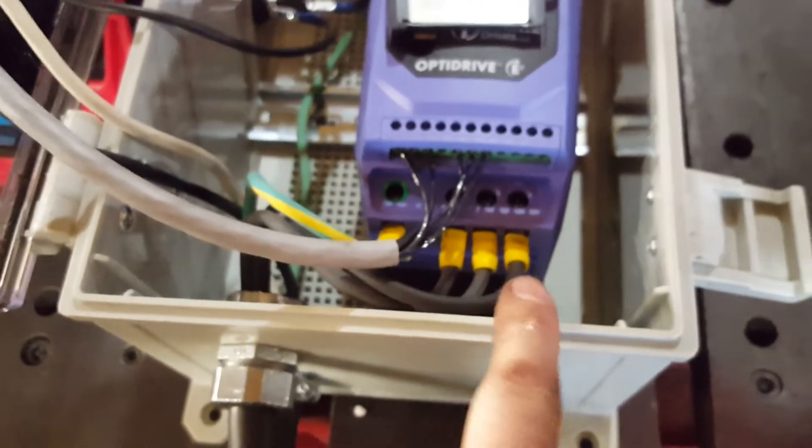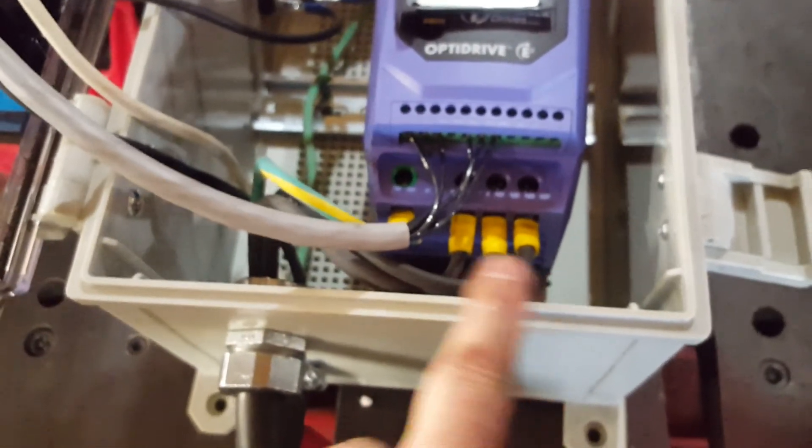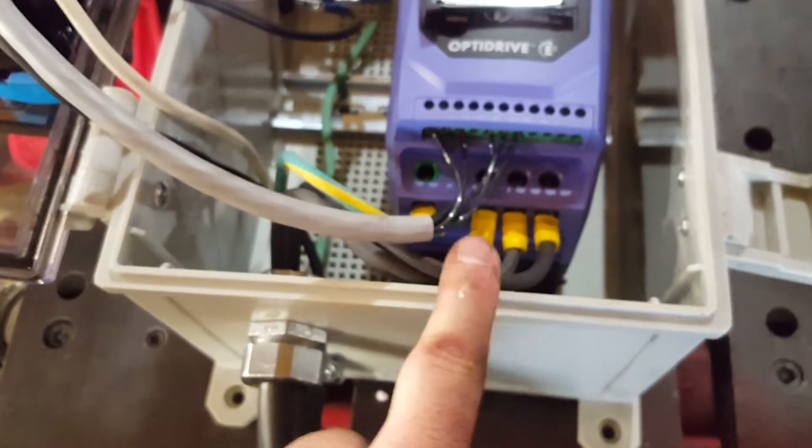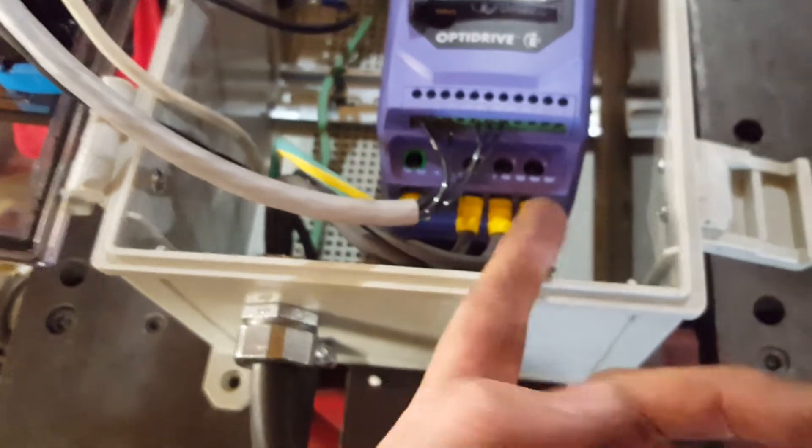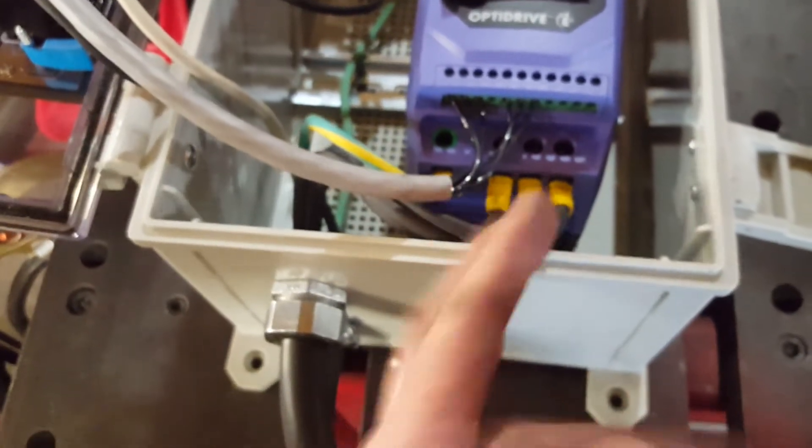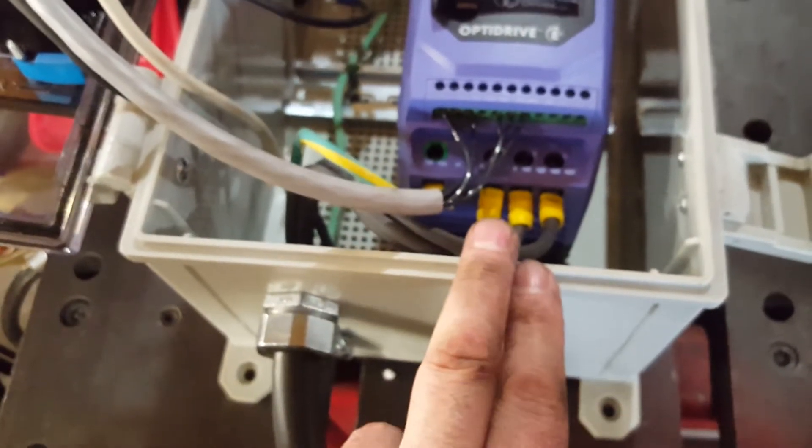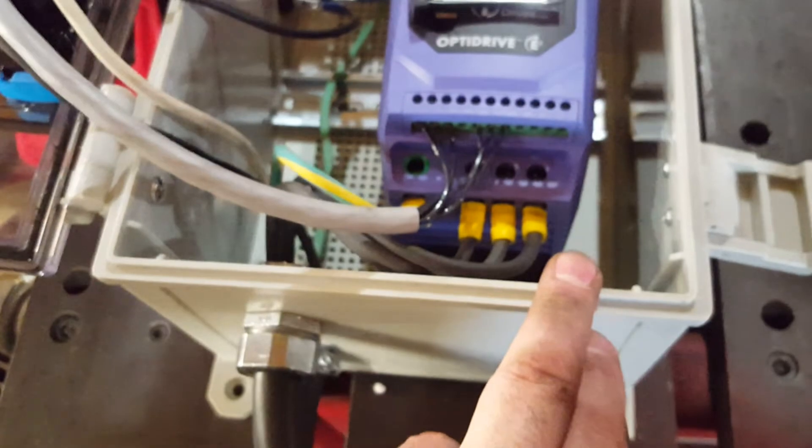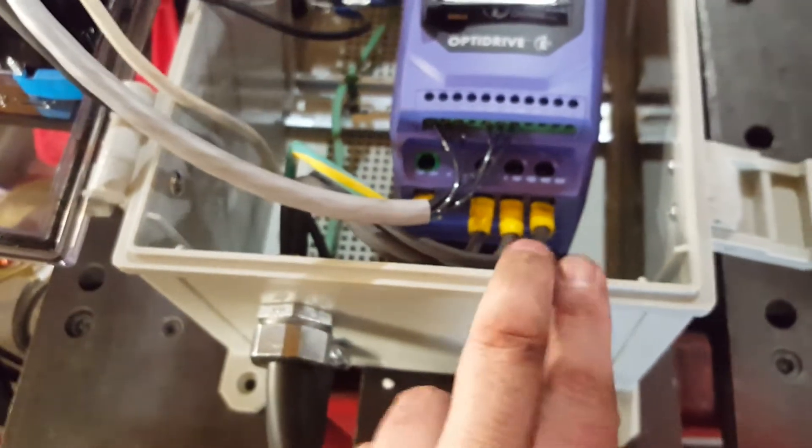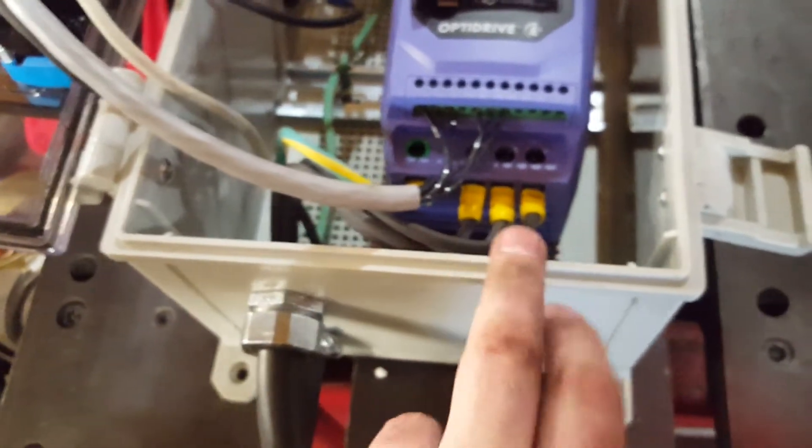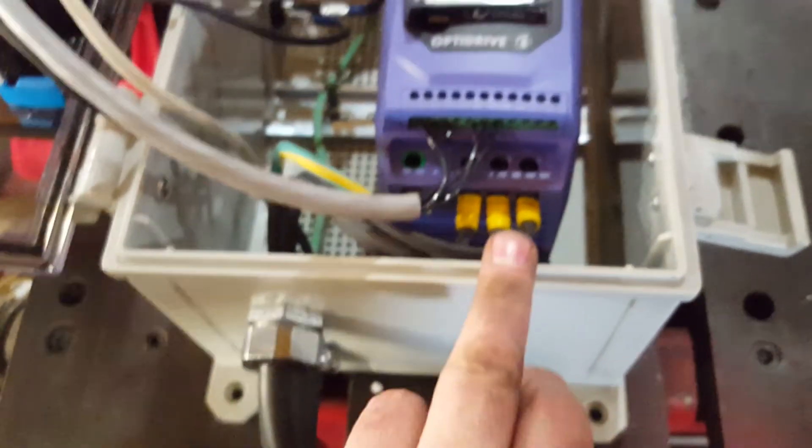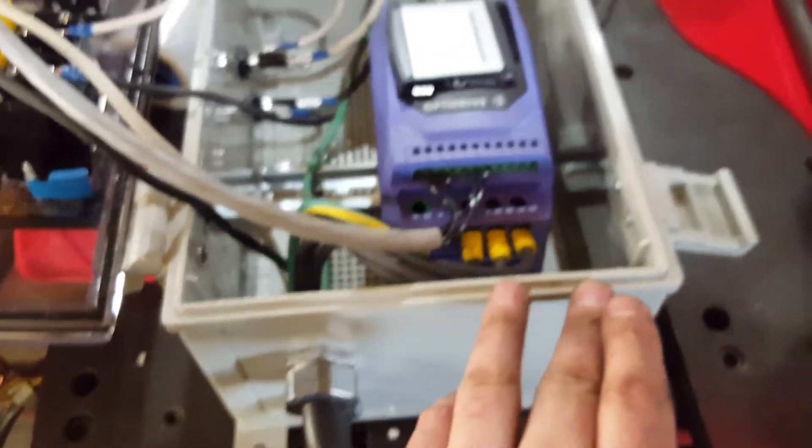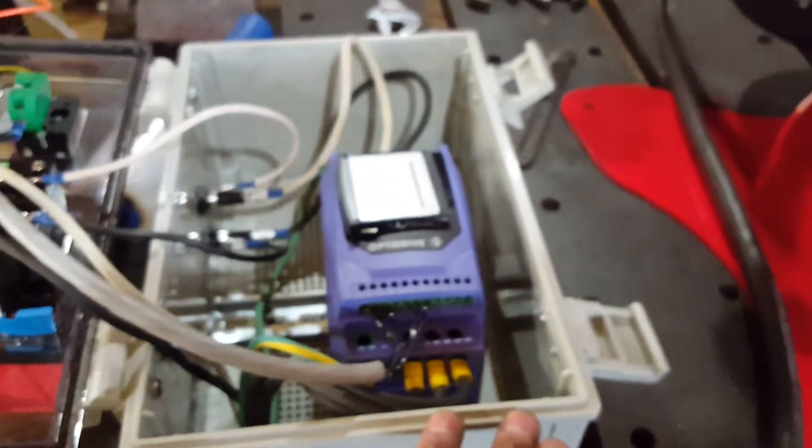instead of going one, two, three, you go one, three, two. Or you could just flip any two, right? So you could flip the first two and do two, one, three, or you could flip the other two and do one, three, two. Basically flipping two of the leads will switch forward and reverse.